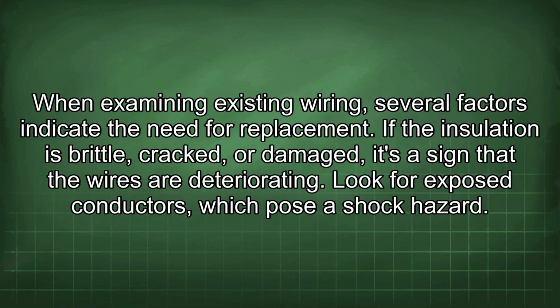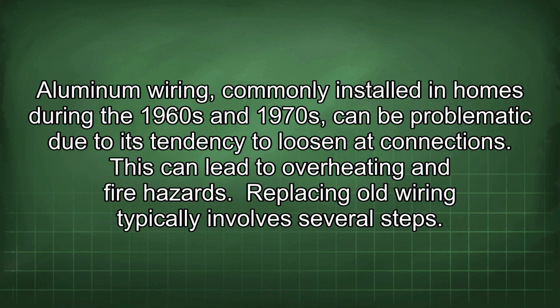When examining existing wiring, several factors indicate the need for replacement. If the insulation is brittle, cracked, or damaged, it's a sign that the wires are deteriorating. Look for exposed conductors, which pose a shock hazard. Aluminum wiring, commonly installed in homes during the 1960s and 1970s, can be problematic due to its tendency to loosen at connections. This can lead to overheating and fire hazards.